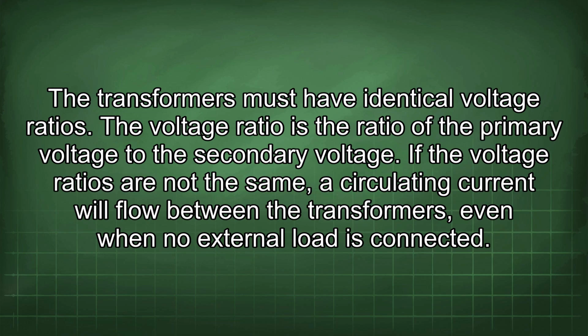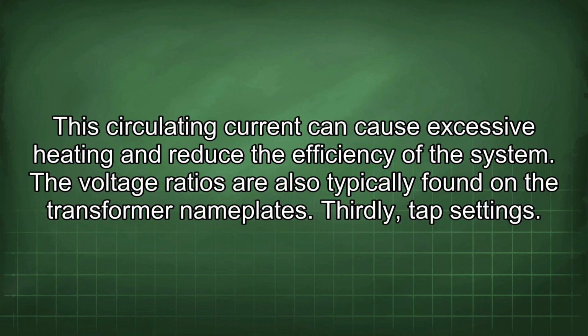If the voltage ratios are not the same, a circulating current will flow between the transformers, even when no external load is connected. This circulating current can cause excessive heating and reduce the efficiency of the system. The voltage ratios are also typically found on the transformer nameplates.